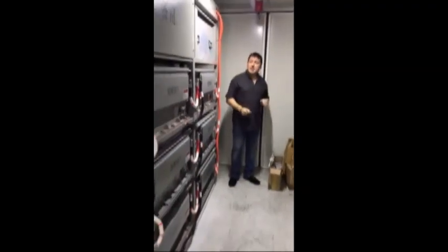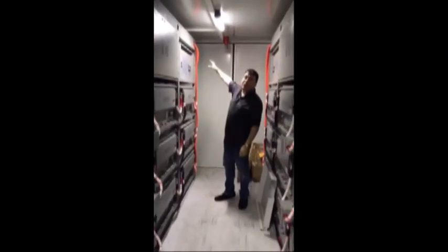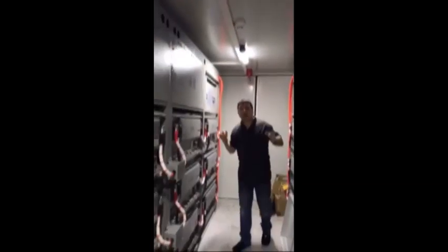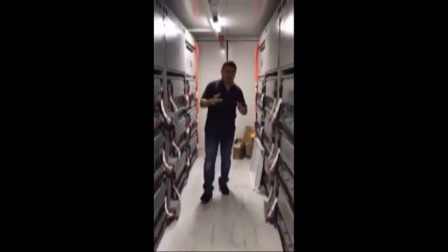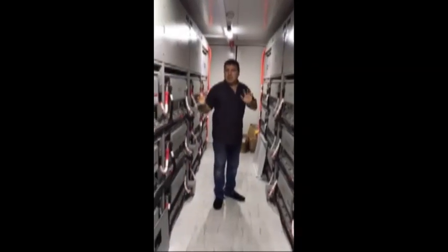This is a one megawatt container module, 40 feet in length. It has one megawatt of stored battery capacity with lithium battery modules, smoke alarm, air conditioning at 2.2 kilowatt, thermostat control to 35 degrees, and LED lighting — all running off the battery bank. We simply lift this out and place it in any environment around the world.